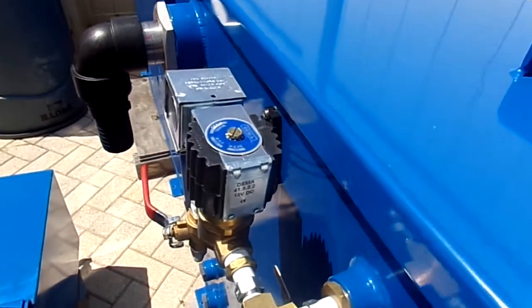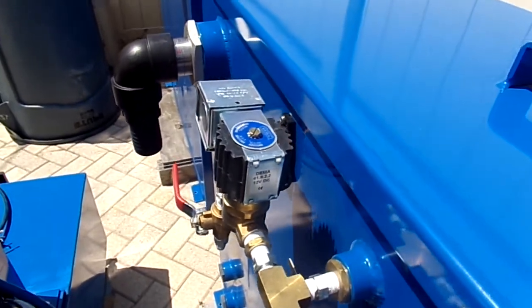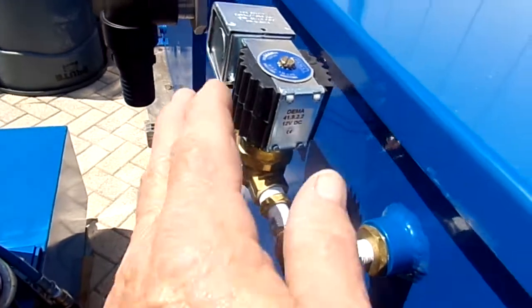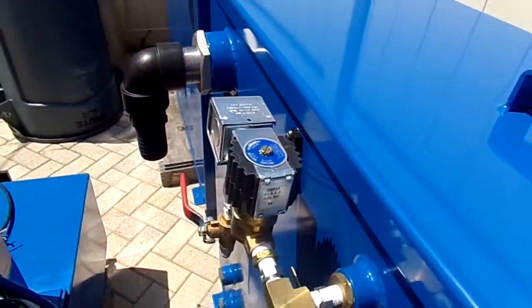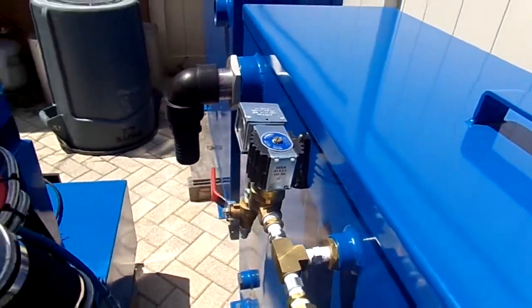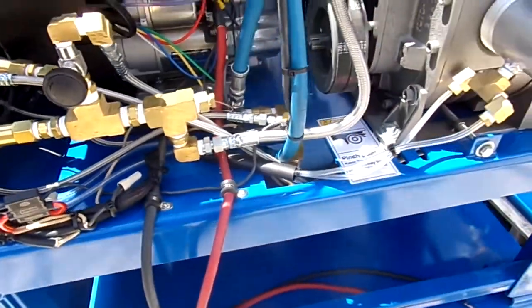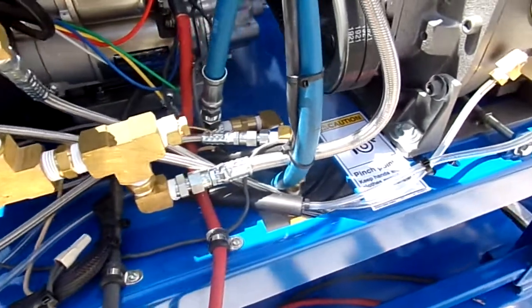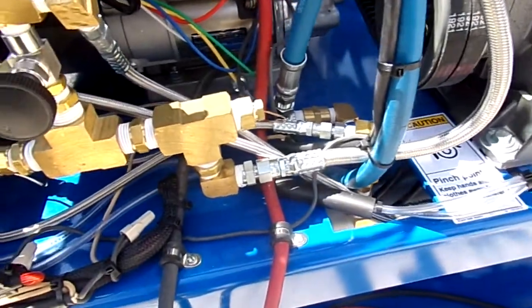You want minimal propagation delay between the time the thermostat sends a 12 volt signal to the solenoid and when it shuts down, because you want working pressure with minimal downtime — you'll be losing pressure while it empties into the tank to lower your water temperature.